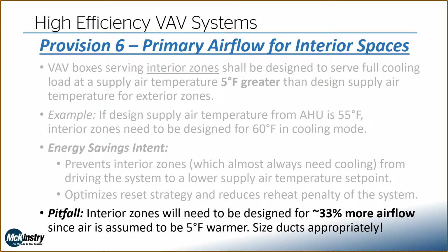The pitfall here, and this is a pretty big one, is that those interior zones need to be designed for 33% more airflow, thereabouts. Since our air is 5 degrees warmer, we need to provide more of it to serve the same load. And where that comes into play is in sizing our ducts. So we need to make sure we're sizing our ducts appropriately for that additional airflow. And it's not just in the branch duct to the VAV box. That's going to reverberate all the way back into the duct mains, all the way back to the air handler. So if this is missed, this turns into a pretty big deal.